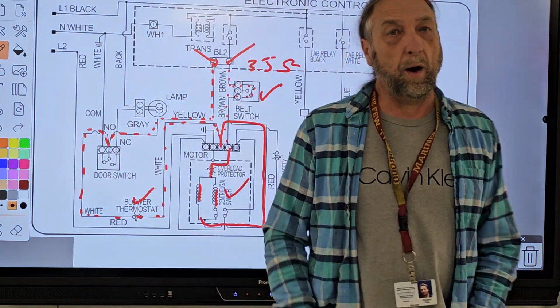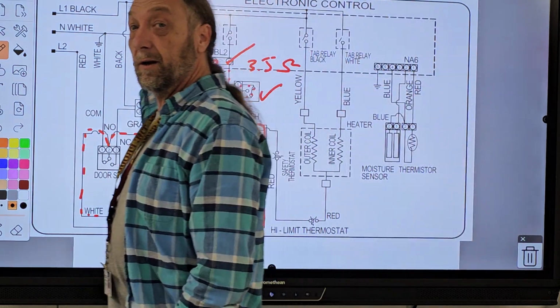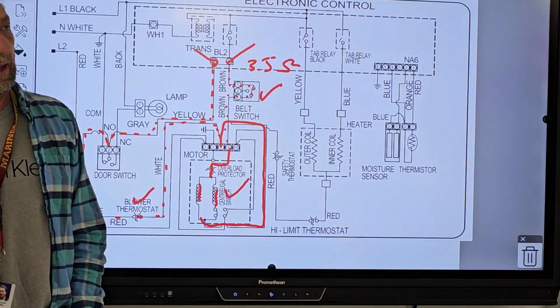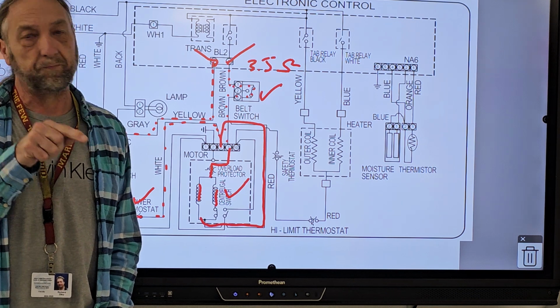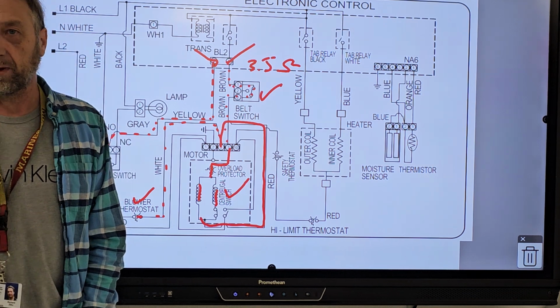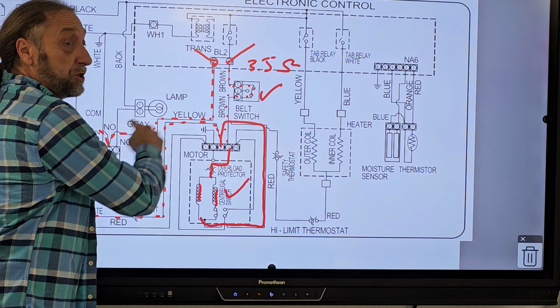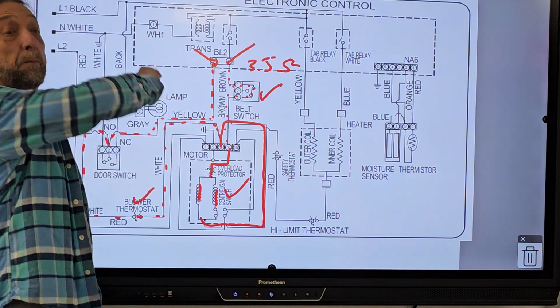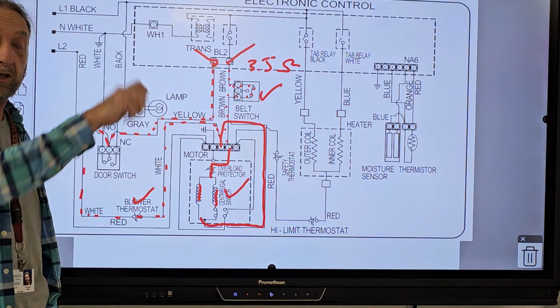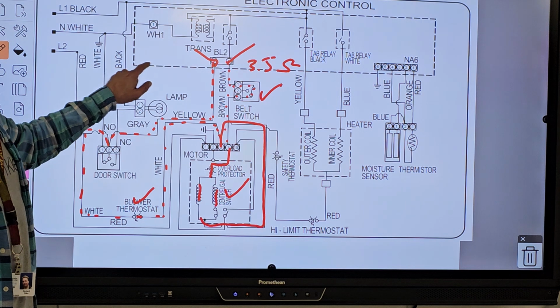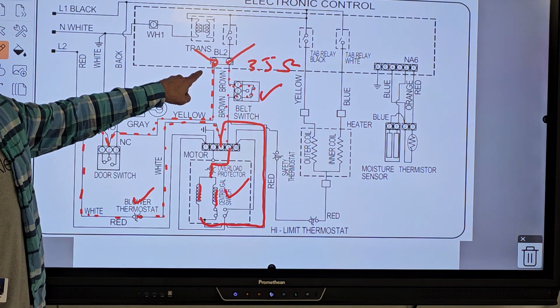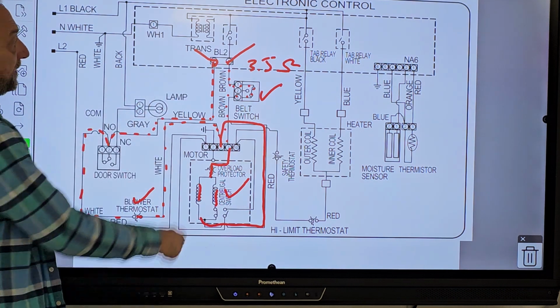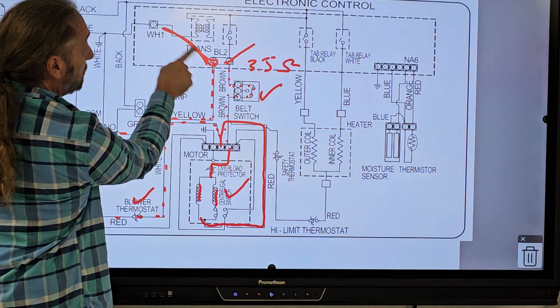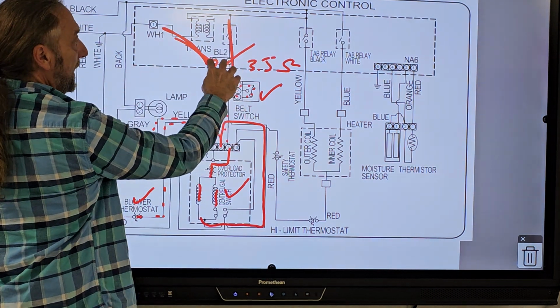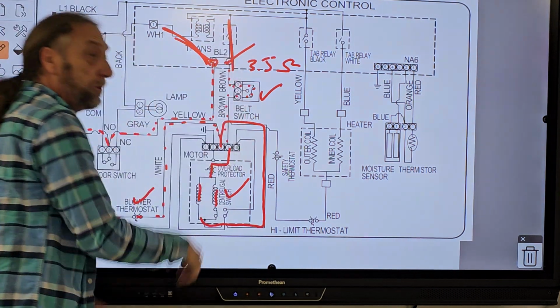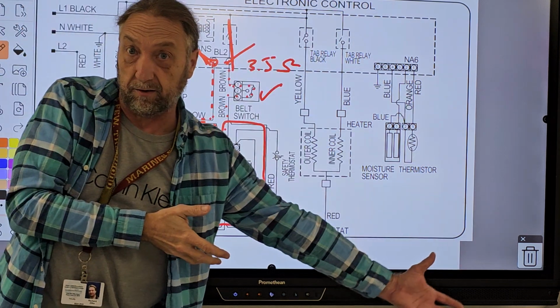Well, why don't I just leave my meter lead right there? And what would I check? Voltage. Not only did I check resistance, but if I switch the meter from ohms to voltage and press start, I should have what there? 120. Because this is line 1 and this is neutral. If I got power here, I know that the board is trying to tell the motor.